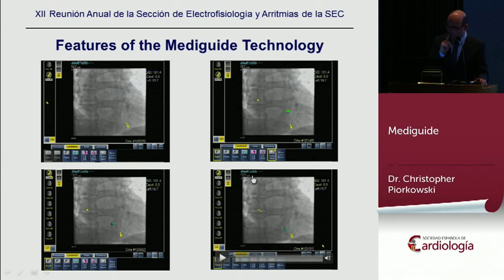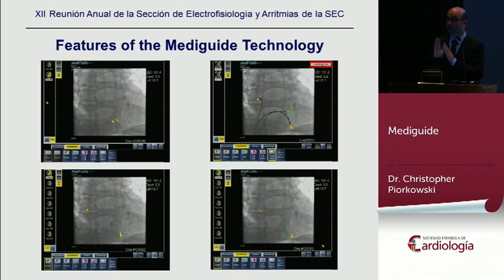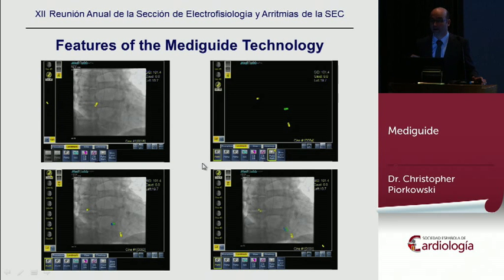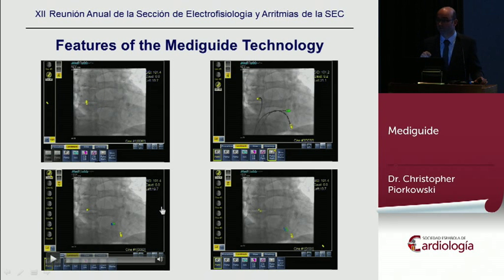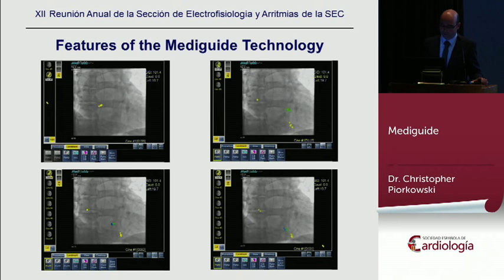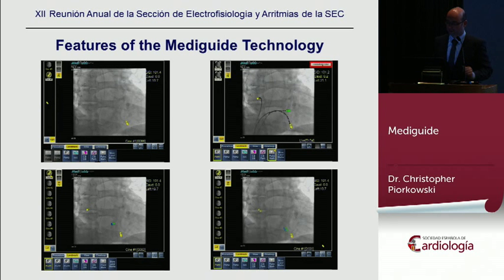To show you the precision of the technology, now the fluoroscopy is indeed used in the second movie, and now you see the catheters on fluoroscopy, you see the tracking of the electromagnetic field in the icon, and you see they continuously overlay each other. It's really precise catheter tracking. Due to the alignment of the technology with the fluoroscopy and due to the ability to track the catheter in real time, the system allows several compensation algorithms which can recognize primary and secondary organ motion, which can distinguish respiration from cardiac motion, and can compensate catheter tracking for these motion components.